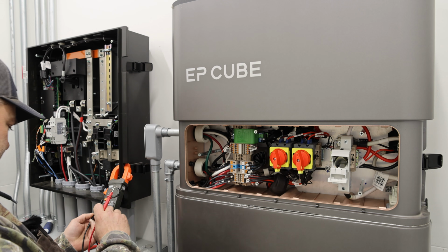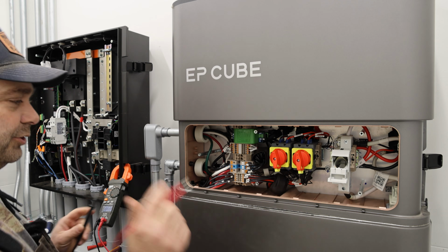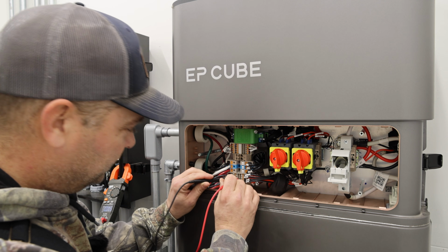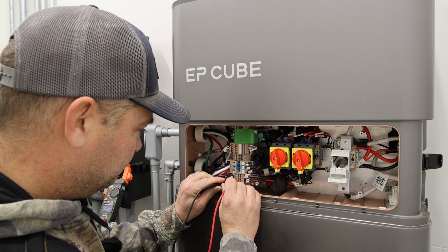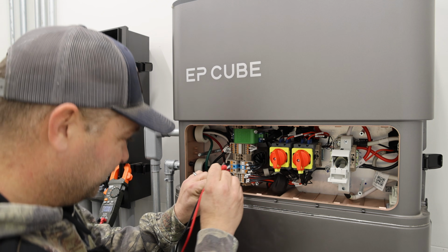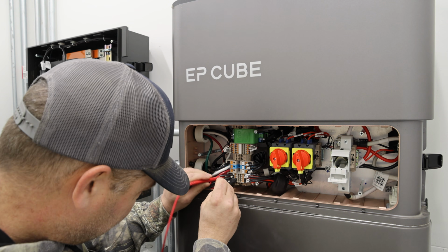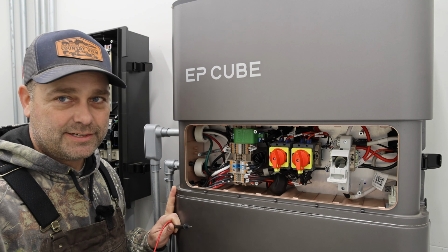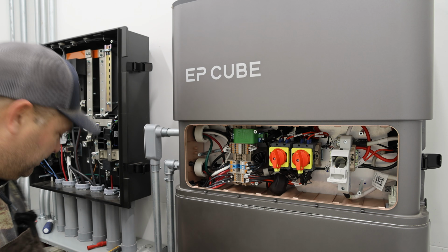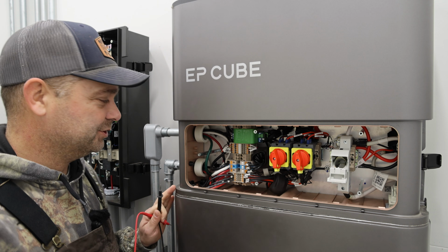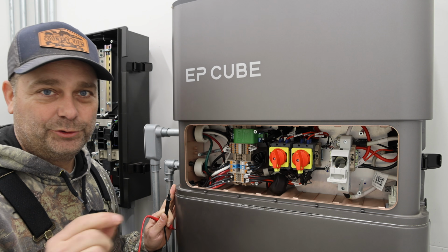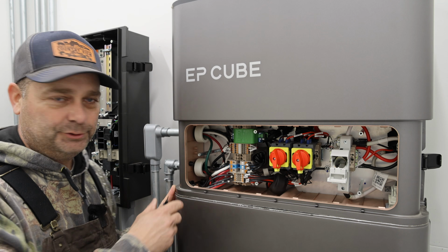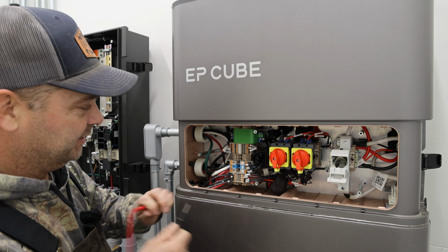All right, and the next thing, I will switch my meter over to DC voltage. We're going to verify that we don't have any voltage on our solar panels, which they should have turned off with their shutdown modules. These push-in terminal blocks here are really hard to test. I couldn't get any voltage reading on there. So I do have a junction box down here. I tested my voltages and everything's dead. I'm only reading 4 volts DC on the solar panels. So that's safe voltage. We should be able to go ahead and disconnect this.